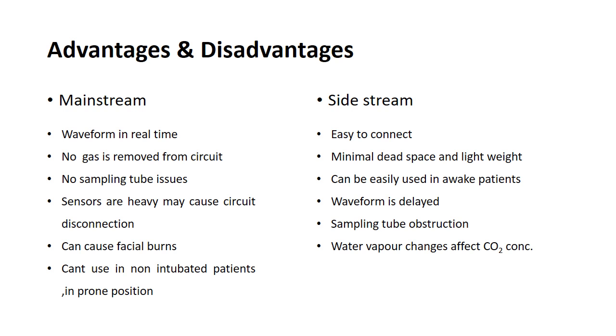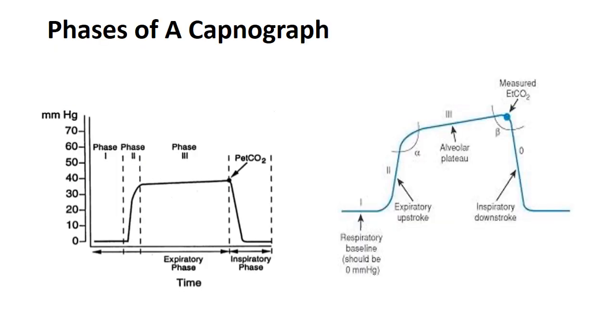The sidestream is very easy to connect, has minimal dead space, is lightweight, and can be easily used in an awake patient. Waveform is delayed, that is a disadvantage. Sampling tube obstruction can occur, and water vapor changes affect the CO2.